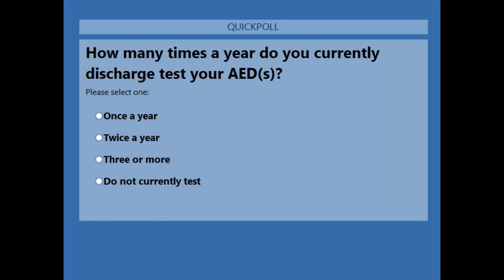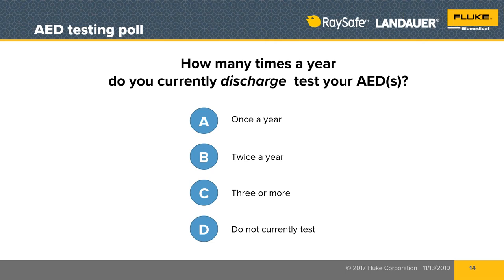Okay, I'm going to close the poll, Jerry. So you have 43% once a year, 36% twice a year, 6% three or more, and 14% do not currently test. Okay, and I believe that for the do not currently test option, the reason is because the manufacturer said you don't need to test these. But we can see with those 72,000 incidents, we absolutely need to test these. So we say kudos, congratulations to those of you who are actually testing the AEDs at least once a year. And look, I know there are so many AEDs in the facilities. And hopefully we're getting some independent service organizations that are also testing those AEDs that are out in public buildings, because those need to be tested also.